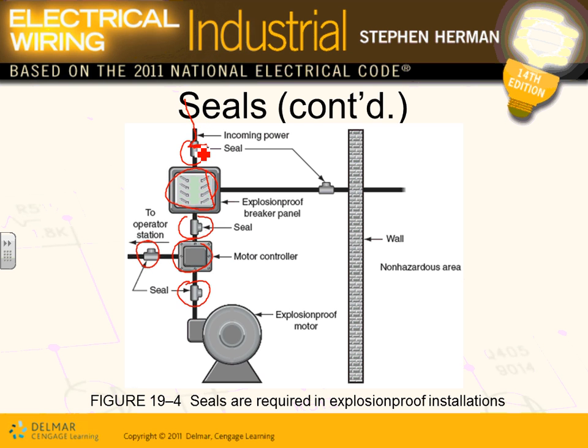Because if it enters the panel, what happens if you have natural gas inside a panel like this? Every time a circuit breaker turns on and off, boom, big explosion. Now the panel can handle it, right? But you lost the panel. So they want to minimize the explosion, so they put seals. So within 18 inches of every arcing and sparking equipment, guys, you have to have a seal. Motor, look at that, explosion-proof motor. So this can handle an explosion inside it. And there's a seal within 18 inches of it.